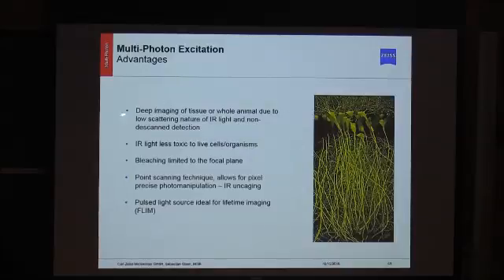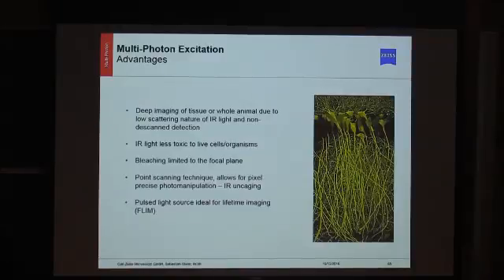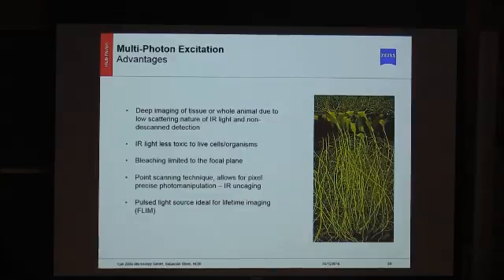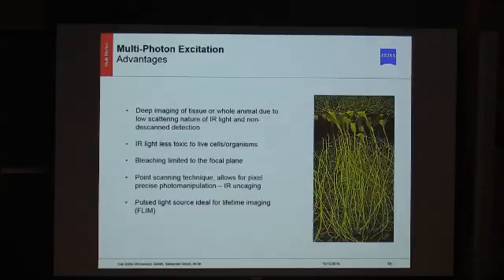The advantages of the multiphoton system: you can use it for deep tissue imaging. Infrared light causes less toxicity to living cells or organisms, so you can image for longer time periods. Infrared excitation causes less photobleaching than visible light excitation. Bleaching is limited to the focal plane only — not to any other plane. You can still apply point scanning photomanipulation techniques, such as uncaging of calcium in deeper layers to study neural activity in the brain. And since it uses a pulsed laser, it is also ideal for fluorescence lifetime imaging (FLIM).